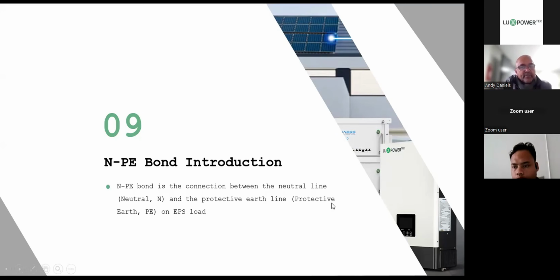And if you enable it, what it will do is when the grid is on, it bypasses the power through, and there's no bond because it assumes that the bond is good. But when there is an off-grid situation, either when the grid is cut or you are installing your inverter in an off-grid situation, you will then enable the neutral earth bond, and that relay will engage. It'll bond neutral and earth on the EPS output, and that should give you 0 volts between neutral and earth. The reason we do that is, in a 230 volt installation, you could have about 115 volts floating there, and that could be dangerous for your consumer.